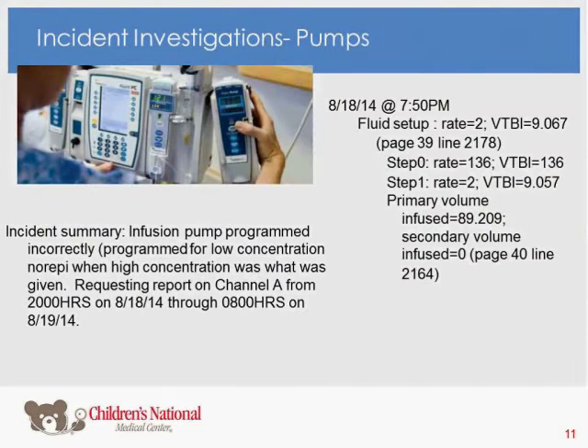impact. I mentioned the incident investigations on the pumps. This is a good example: someone will call and say, hey, this pump was supposed to pump at X volume, and the bag was empty before it was supposed to be empty, and a lot of things could go wrong with that. Usually the first thing is that the pump malfunctioned. Again, pumps usually don't break. But I call them little BMWs when I do the nursing education, in that this medical equipment is so expensive that what we do to fix it really is a small part. But the manufacturers, in order to get through FDA, naturally aren't going to make too many mistakes.